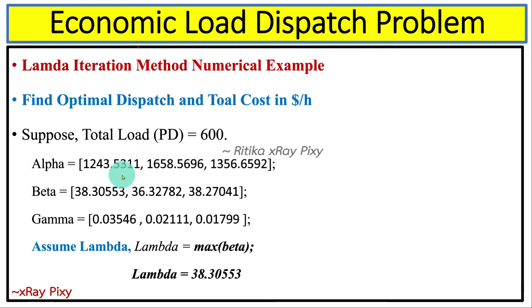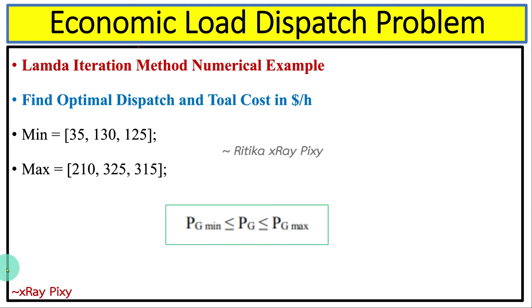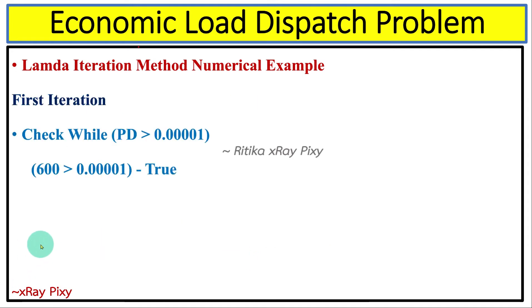Our aim here is to find the optimal dispatch and total fuel cost. Suppose total load is 600 MW, and we have values for alpha, beta, and gamma for three units as shown. We assume the initial value of lambda to be the maximum value in beta, which is 38.30553. We also have inequality constraints with minimum and maximum power values for each unit that must be satisfied.